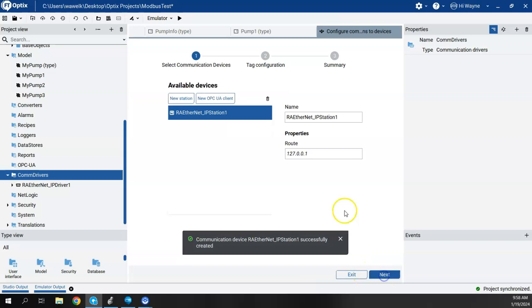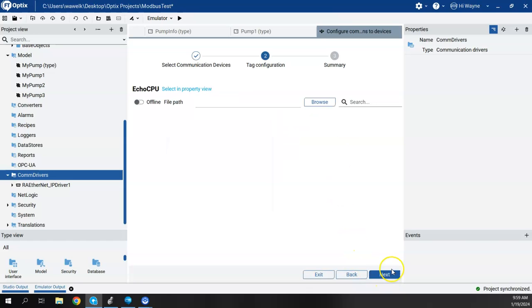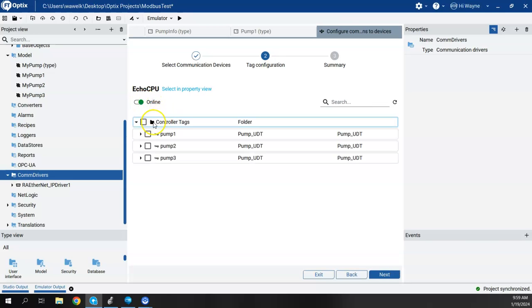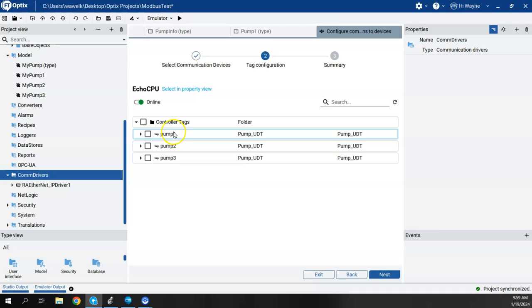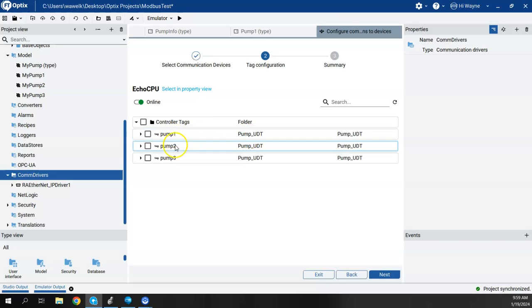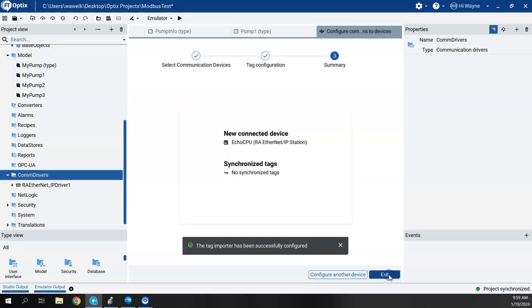And I'm going to hit Next. Now it gives it a name, RA Ethernet IP Station 1. I'm going to go ahead and call it Echo CPU, just to kind of make it a little bit shorter and more in line with what it actually is. So this is where we can import our tags. So I'm going to go ahead and do an online import. It went out and read the controller tags. So these are all that I've created so far in here. So those are our UDTs, Pump 1, 2, and 3. Go ahead and select All and say Next. And then everything's been successful.